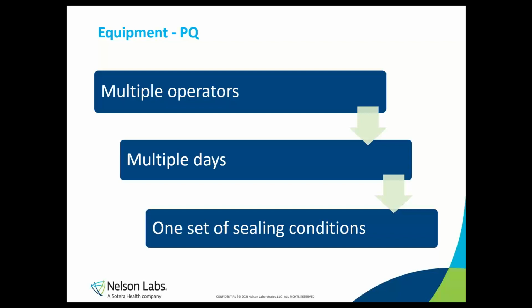The PQ, or performance qualification, is where we challenge the ruggedness and repeatability of the process. Here, we need to make samples on multiple days to show that day after day we can get the same seal quality. We also want to add in multiple operators to show that regardless of who is pushing the buttons, we will get the same final product. We need to seal all samples at the same settings, so the only variable is the operator or the day of testing. That way, we can make a good comparison of the data.